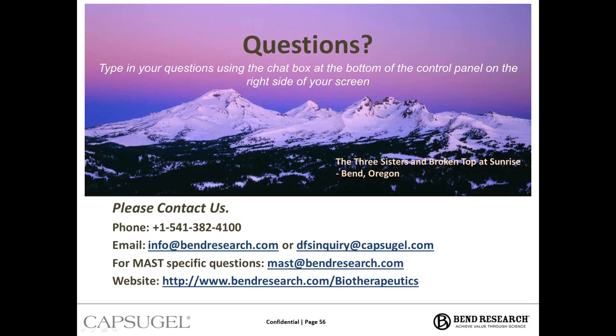Regarding scale limitations: we currently use the SP100 or SP200 at scales from 1 liter up to 2,000 liters. The system pulls a consistent sample in a similar way regardless of reactor size. The SP200 pulls 5 ml sample increments, so once you get below a 1-liter reactor and want more than one sample a day, you start to become limited in volume. Right now it really is from 1 liter up to as large as you need.